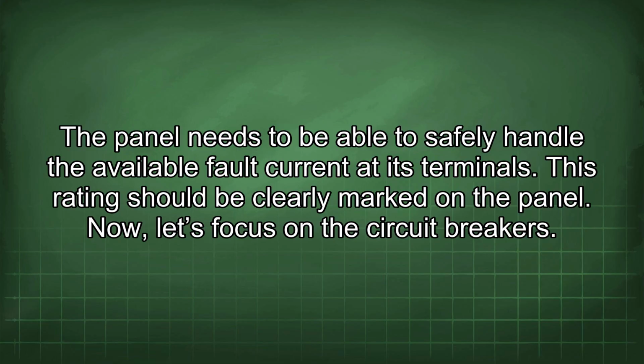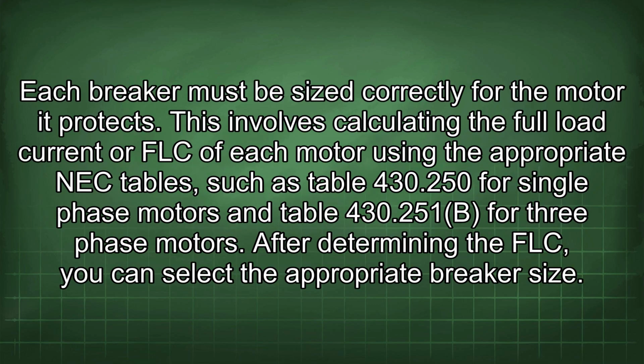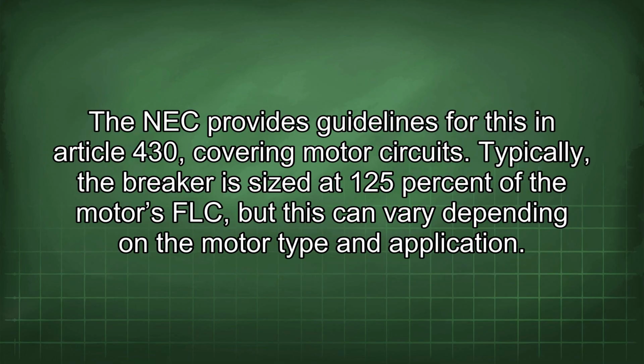Now let's focus on the circuit breakers. Each breaker must be sized correctly for the motor it protects. This involves calculating the full load current, or FLC, of each motor using the appropriate NEC tables, such as Table 430.250 for single-phase motors and Table 430.251b for three-phase motors. After determining the FLC, you can select the appropriate breaker size. The NEC provides guidelines for this in Article 430 covering motor circuits.